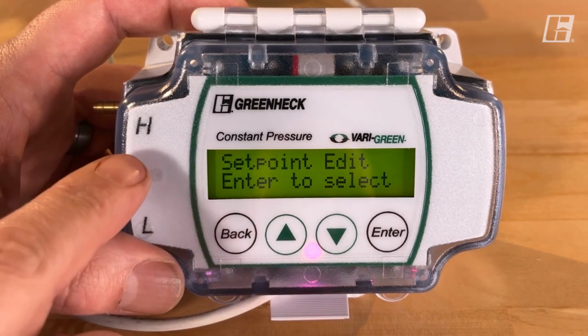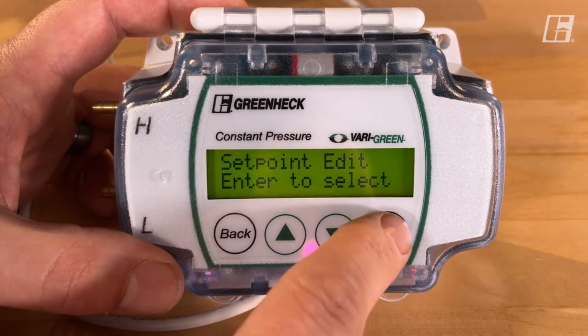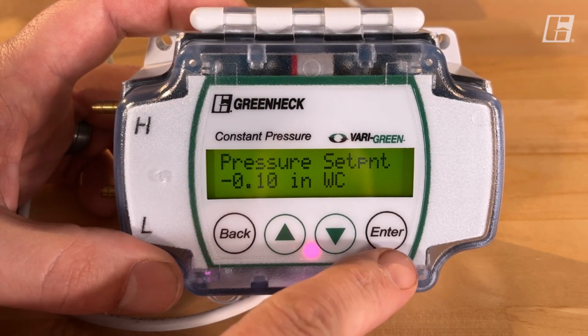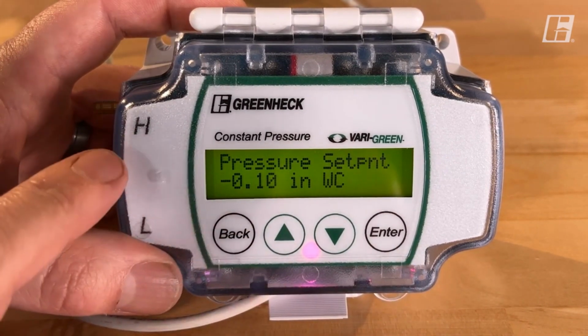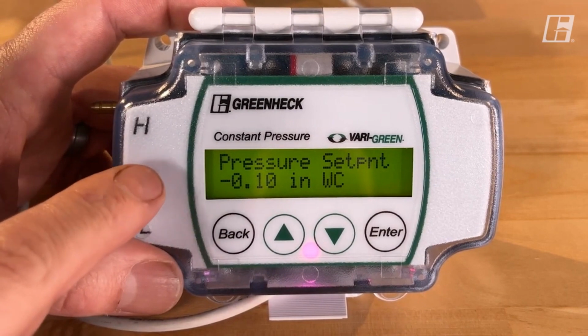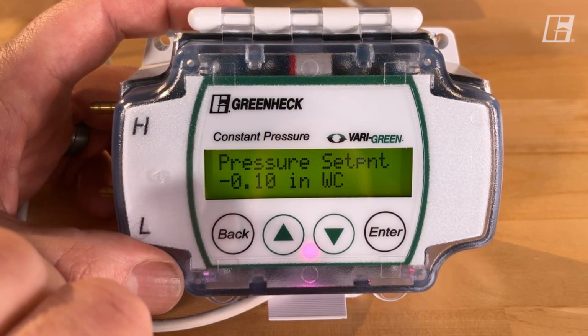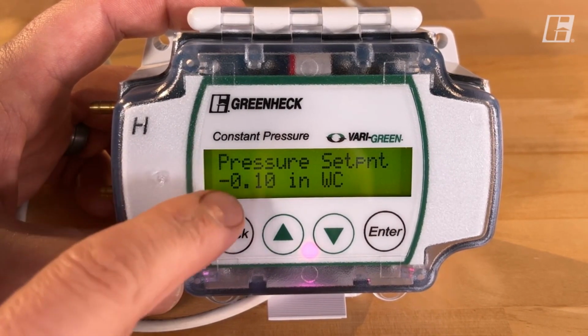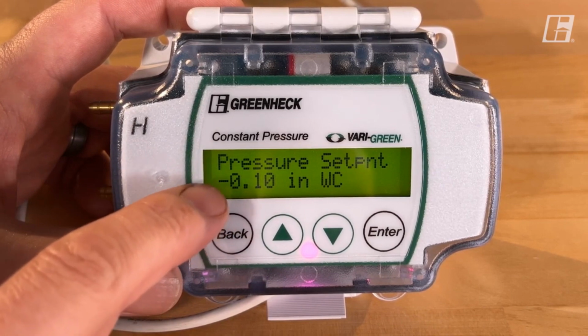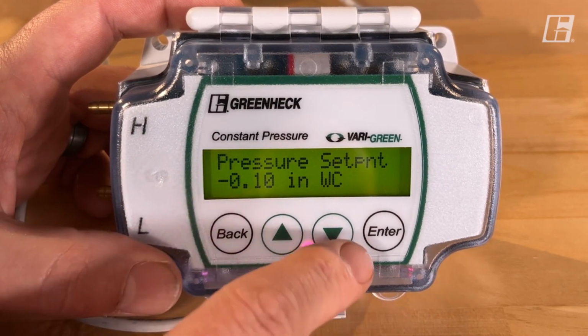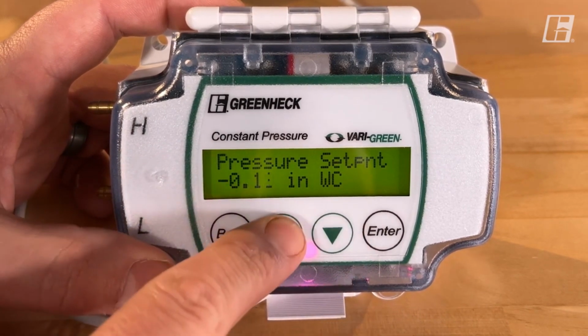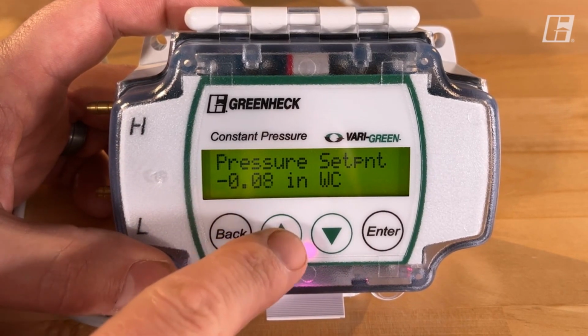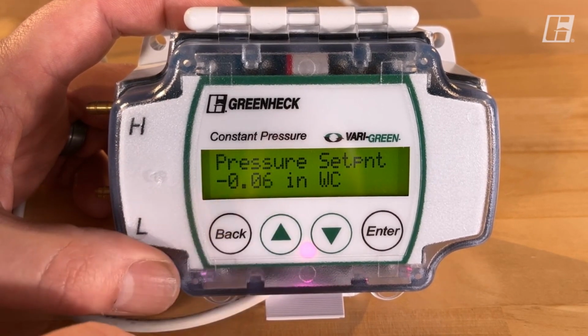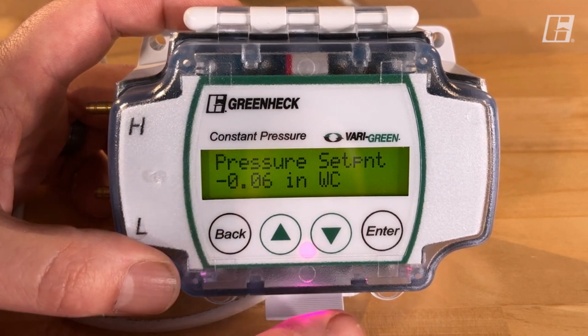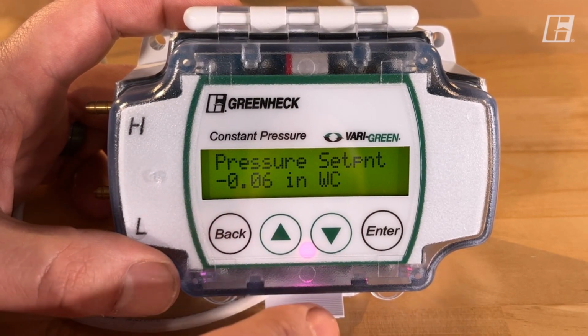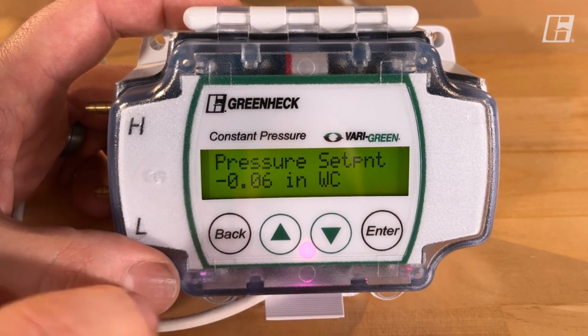So we are going to go into set point edit. So we'll just simply hit the enter button to enter the menu. The first thing it asks us is, what is the pressure that you want to maintain? So in this scenario, right now from the factory, it's negative 0.1 inch. We're going to actually reduce that to negative 0.06.